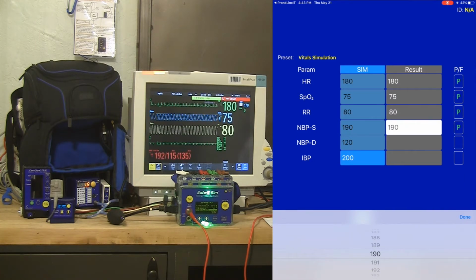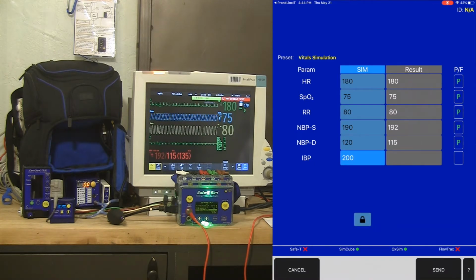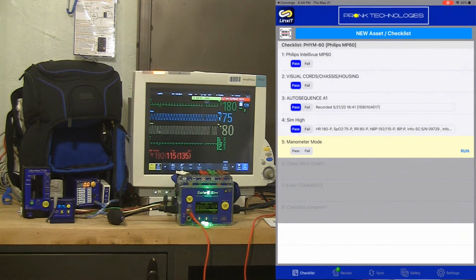So my NIBP is done. I got a 192/115, so I'm going to use my scroll wheel for indicating that exact measurement. And in the case of IBP, I'm just going to tag it as a pass. All that data gets stored into an electronic record that we are building as we go through this checklist.